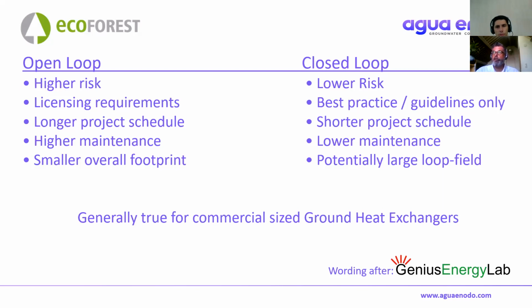Sometimes we have to notify the regulator, sometimes we have to submit plans, but generally we don't have to get these two sets of approvals, because we're just drilling, putting loop in the ground, and then backfilling those boreholes. So closed loop tends to be designed and installed under sets of standards, guidelines, or best practices, depending on which country you're in. I'd argue that's a lower level of regulation than applying specifically for your scheme.